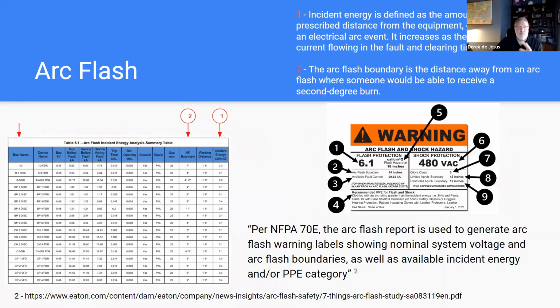The last part brings together the short circuit study analysis and the coordination table into the arc flash hazard analysis. So this is the part that's also required by NFPA 70E, because this generates what everyone's very familiar with on the screen, the arc flash label. The arc flash label is applied to the front facing or sometimes the rear access of equipment, panel boards, switchgear covers. They will then have in this table a lot of information that pertains to you as a commissioning agent that you need to be aware of.